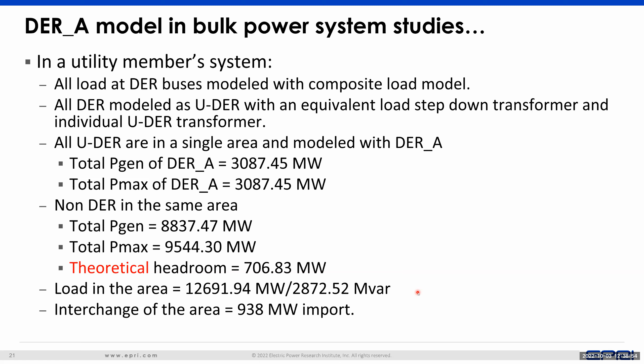We assumed these parameters: all DER trips if the voltage stays below 0.89 per unit for more than 2 seconds, and all DER trips if the voltage stays above 1.2 per unit for more than 2 seconds. All these individual variable names are given in the previous references on the slides about the model, specifying what they relate to.